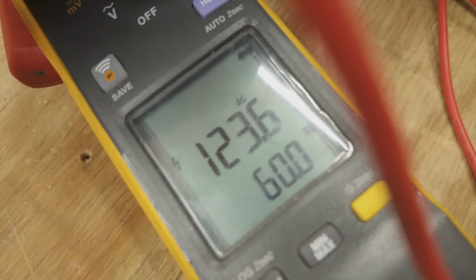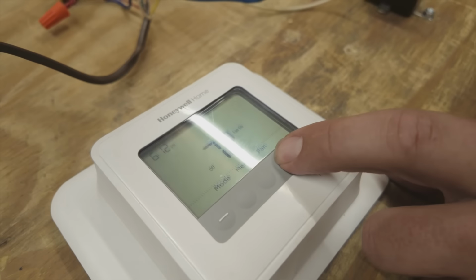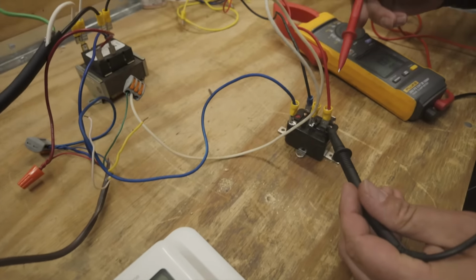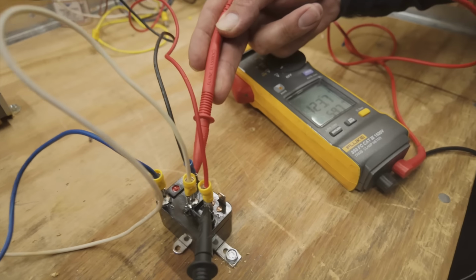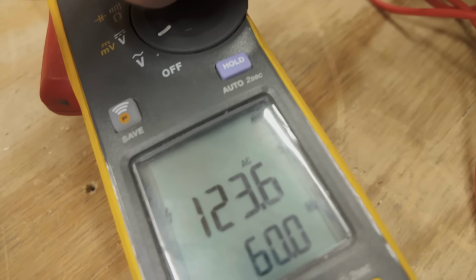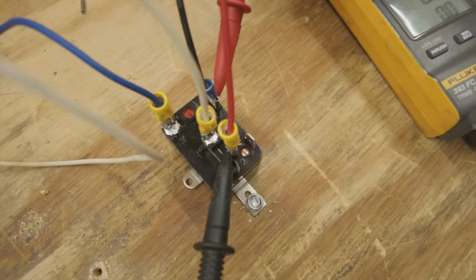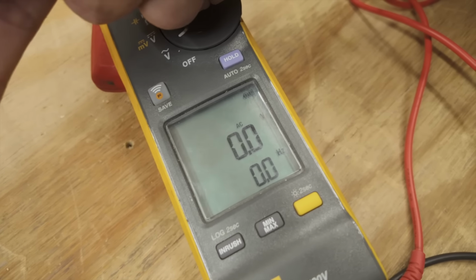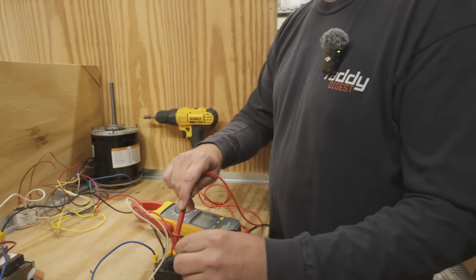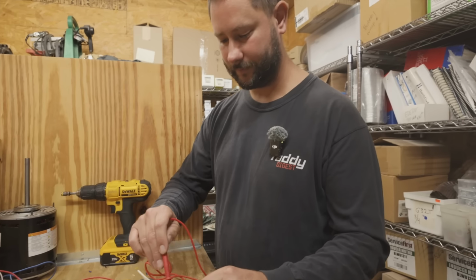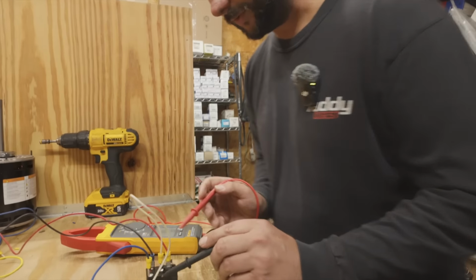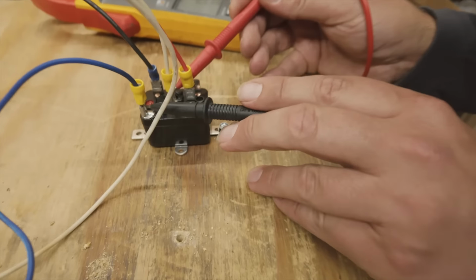123 volts, right? Now let's turn the fan to on. 123 volts. Relay is going to click. Voltage goes away, 0. Why? Because we completed the circuit. And we have voltage. How do we know we have voltage? Check the coil. Let's check the coil real quick here. And there it is.